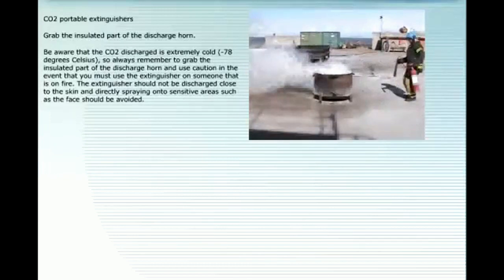The extinguisher should not be discharged close to the skin, and directly spraying onto sensitive areas such as the face should be avoided. When using a CO2 extinguisher, sweep the discharge horn across the fire. The discharge time for a 6 kilo extinguisher is about 20 seconds.